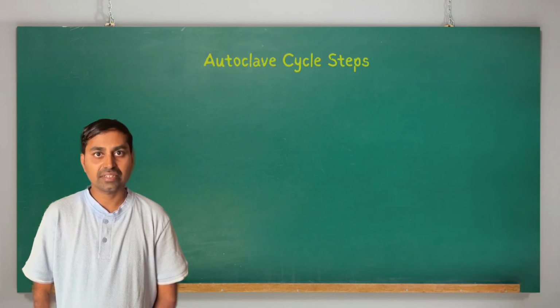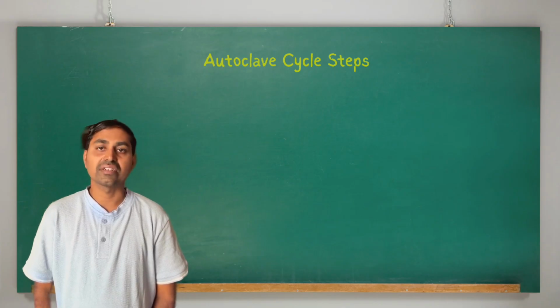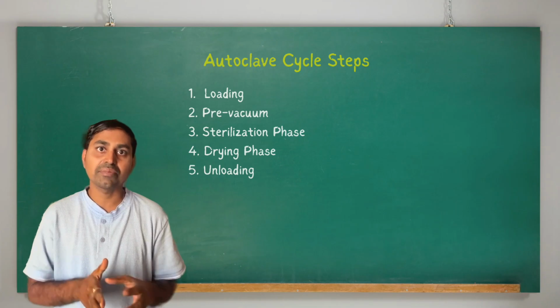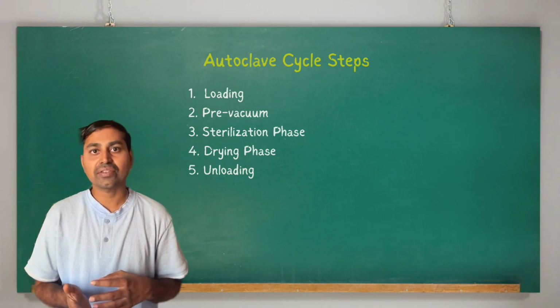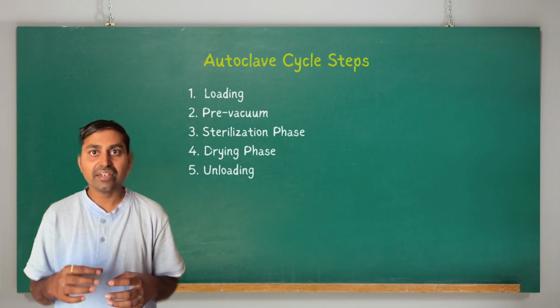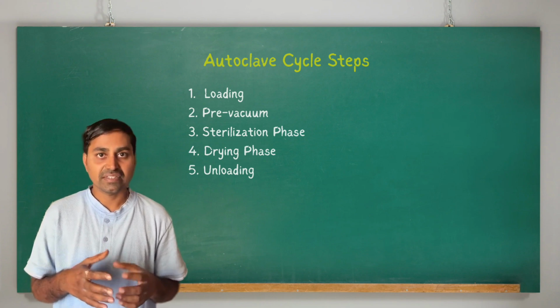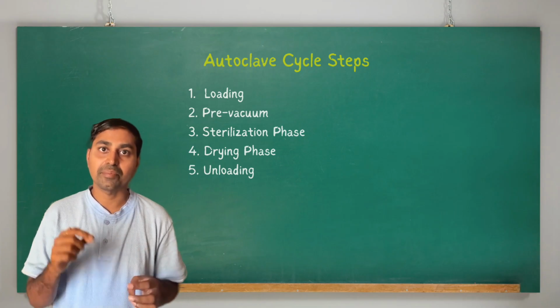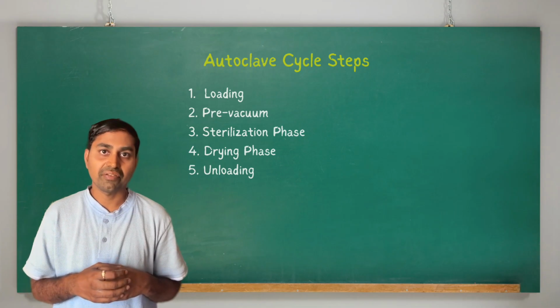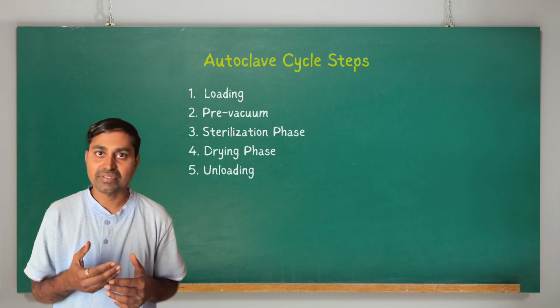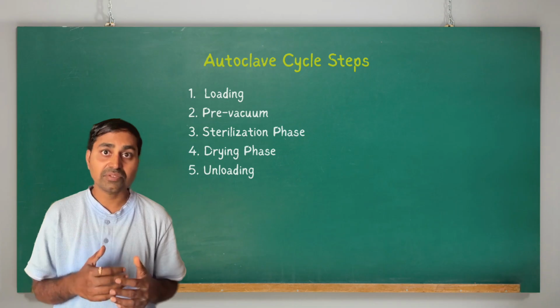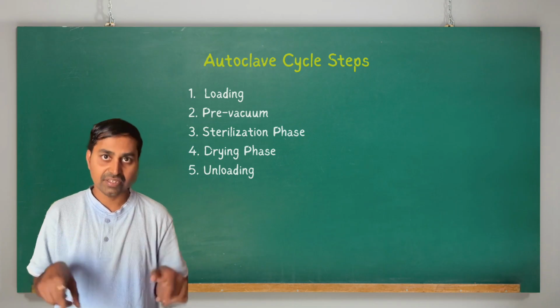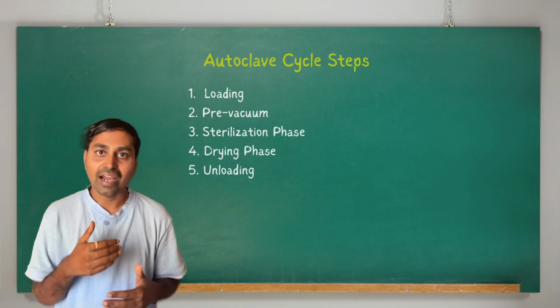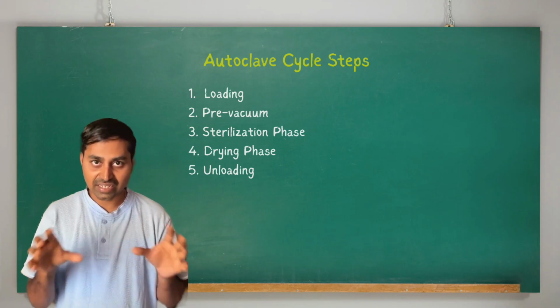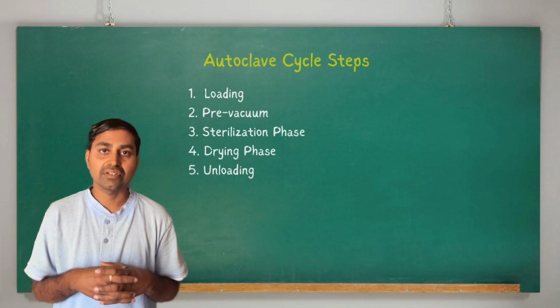Next, we will see the steps in the autoclaving process. First step is loading. Arrange items loosely for steam penetration. Second step is pre-vacuum, where the machine removes air for better steam contact. Third step is the sterilization phase, where we set temperature at 121 degrees Celsius for 15 to 20 minutes. Next is the drying phase, where the machine removes moisture to prevent rusting of the inner lining. And the last phase is unloading the sterilized instruments using sterile gloves to handle them.